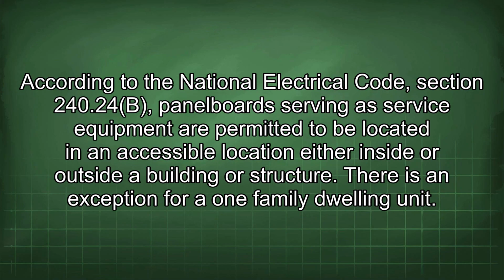According to the National Electrical Code, Section 240.24(B), panel boards serving as service equipment are permitted to be located in an accessible location either inside or outside a building or structure. There is an exception for a one-family dwelling unit.